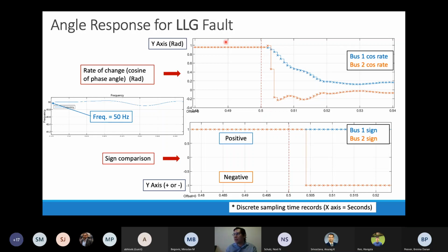We can see that when the fault happens, we do have some small variation in our cosine function. And if we take the sign of this, we are able to detect that the current is flowing the other way, as presented in the previous example. Whereas the previous state was feeding from 1 to 2, in the second state we have one feeding to 2, but in the other one we can see that the current flipped the other way, because both are feeding the fault, and this changes into negative.